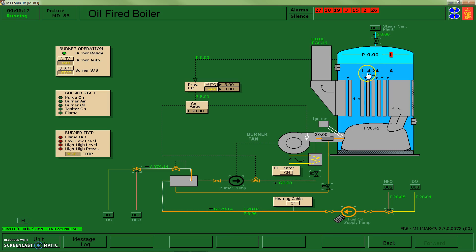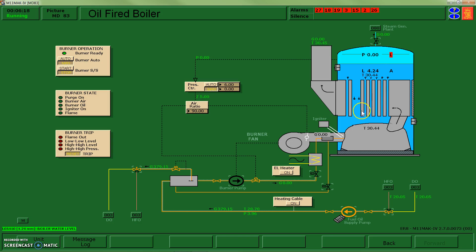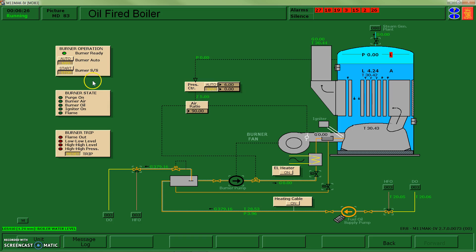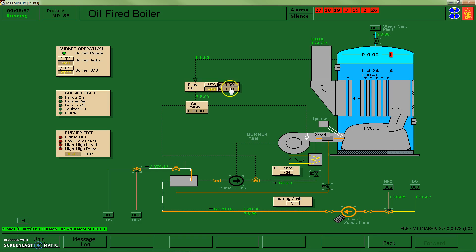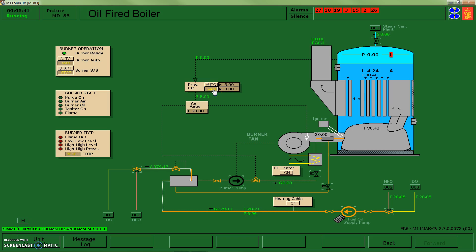So I have a level here, my level is pretty good, I've got water in the boiler, and what I'm going to do is I'm going to attempt to start my boiler. So a couple of things I want to do: I want to make sure that I have my pressure control in manual at this point and on low firing, so 0% output. I don't want it to have a high output while I'm warming it up, so 0% in manual.